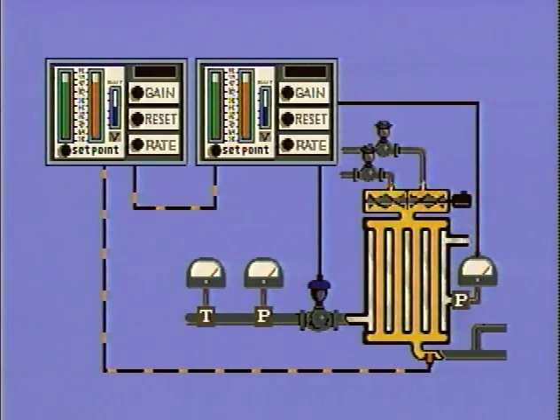The outer or primary feedback loop still responded to the temperature of the product in the heat exchanger. However, instead of directly positioning the steam valve, the output of the primary controller was used to adjust the set point of the secondary controller. The secondary controller then positioned the valve. Under most circumstances, the secondary loop was doing most of the work involved in maintaining a steady product temperature. Its major responsibility was to minimize disturbances in the steam line. In contrast, the primary loop's major control action occurred whenever there was a disturbance or load change in the product, for it was then that the set point of the secondary controller had to be changed.